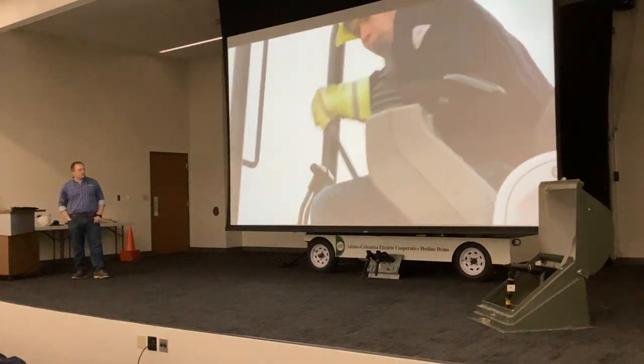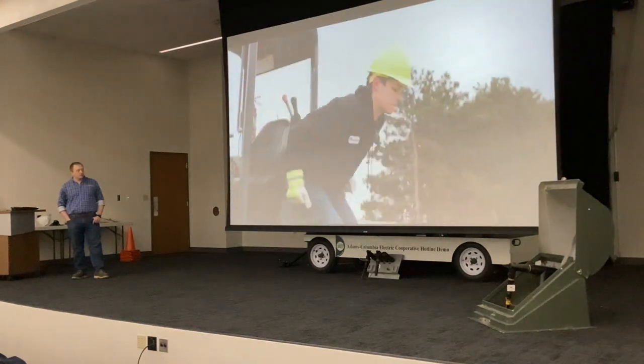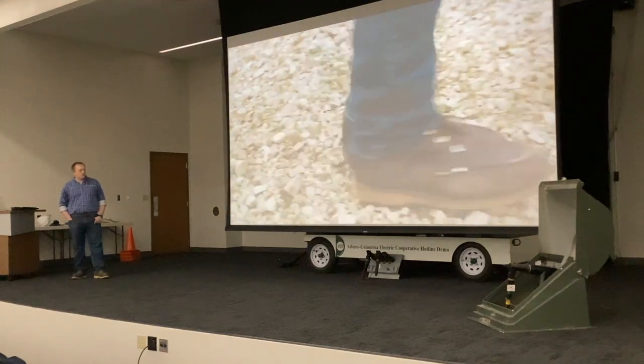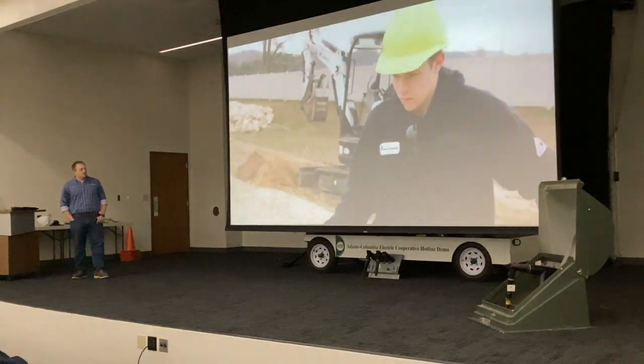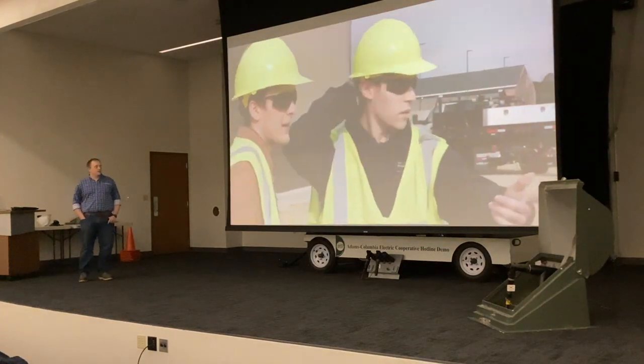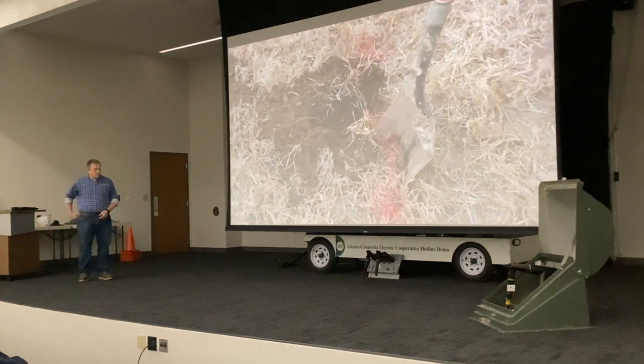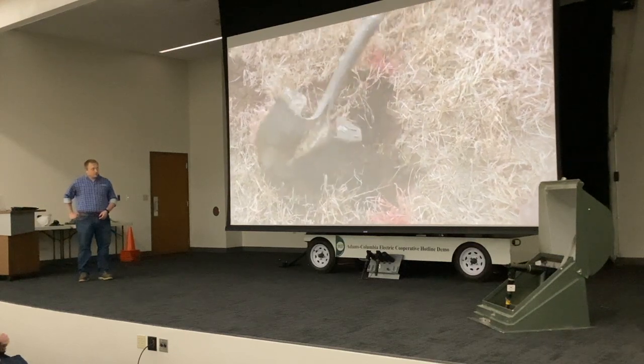If you are unable to stay on the equipment due to fire, jump clear of the equipment, making sure to land with both feet together and never touching both the equipment and the ground at the same time. Shuffle or hop away, keeping your feet together until you are at least 50 feet away. Never go further than toe to heel apart. Calling 811 to locate underground utilities before digging, and hand digging any time you are within 18 inches of a marked utility would have prevented these accidents.